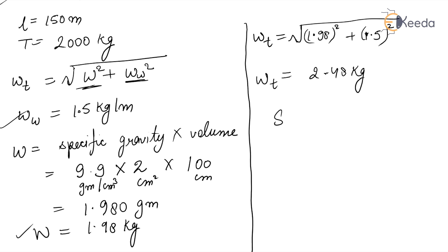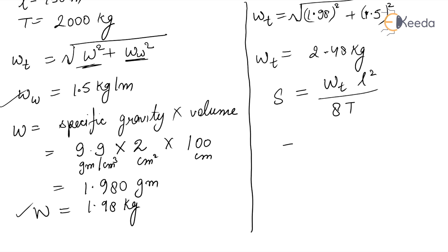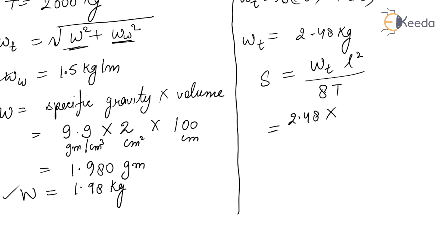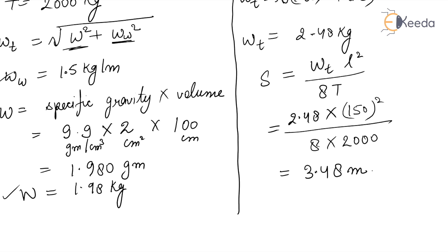SAG = WT × L² / (8T). Substituting WT = 2.48 kg and span length L = 150 m and tension T = 2000 kg, we get SAG = 2.48 × 150² / (8 × 2000). This equals 3.48 meters.